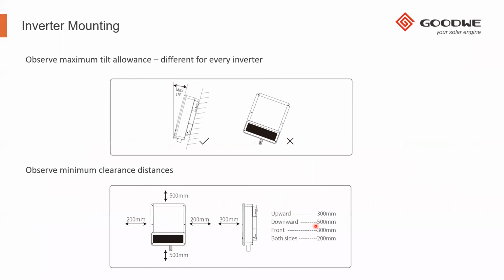In terms of the mounting, we do have maximum tilt allowances for every inverter, so please look inside the instruction manual to find the maximum tilt allowance. For example, in this graphic on the screen, it's a DNS inverter, and this DNS inverter can be tilted at a maximum of 15 degrees to the vertical. Also, please observe the minimum clearance distances that we state in the manual. These clearance distances are there for a reason: to allow the inverter to dissipate heat efficiently and to cool itself by way of convection cooling.